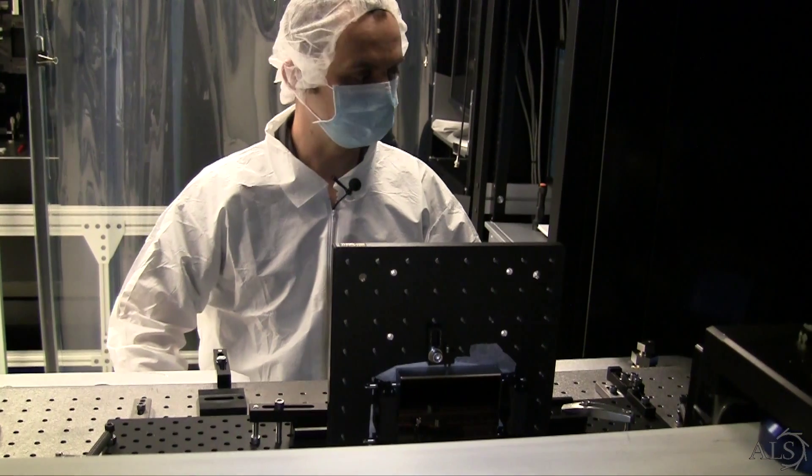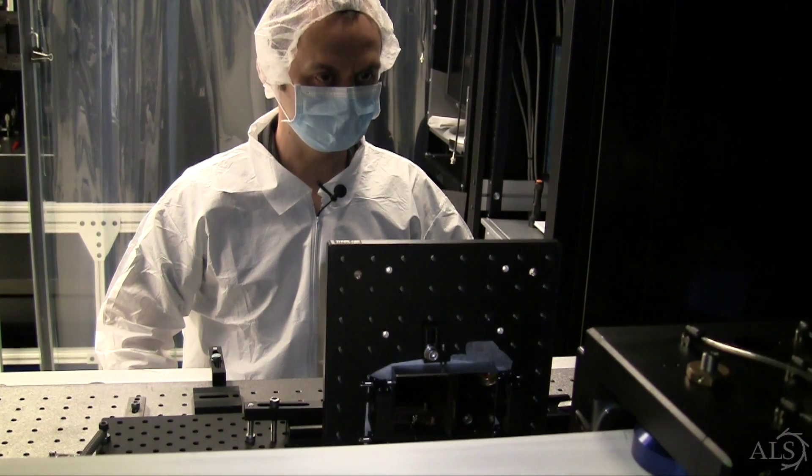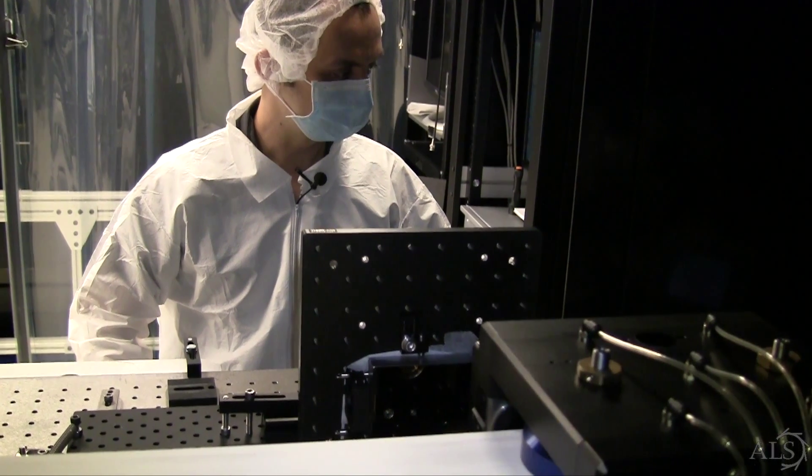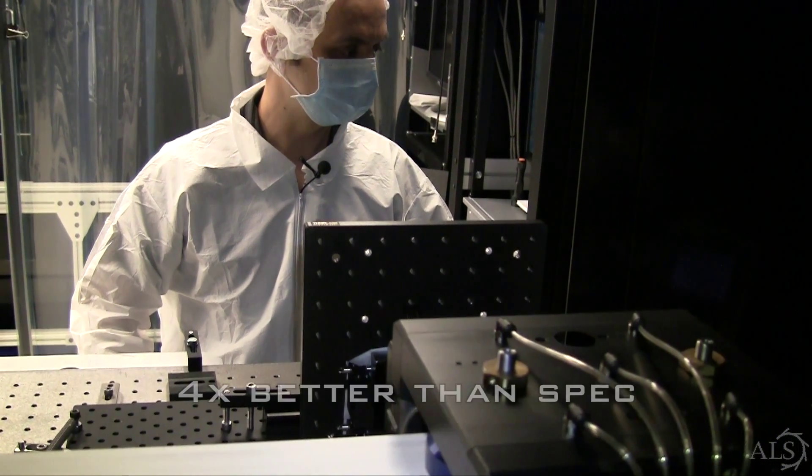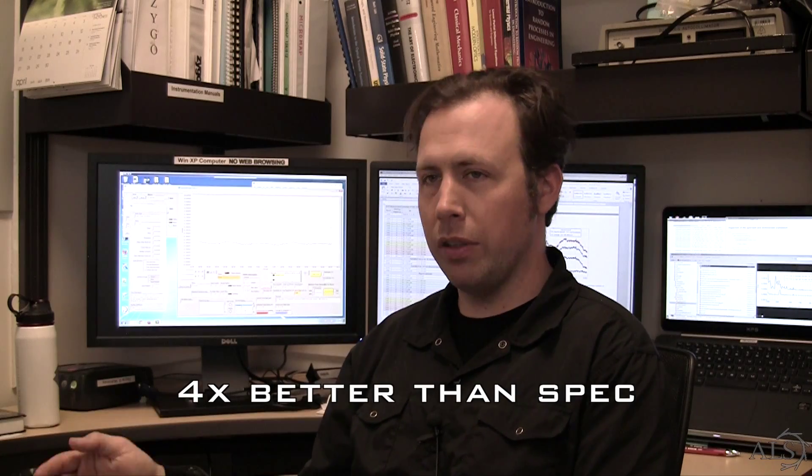On the optical table, where the instrument and the optics are going to be sitting 45 minutes to an hour, we're seeing about one millikelvin temperature variation over the course of that single scan.